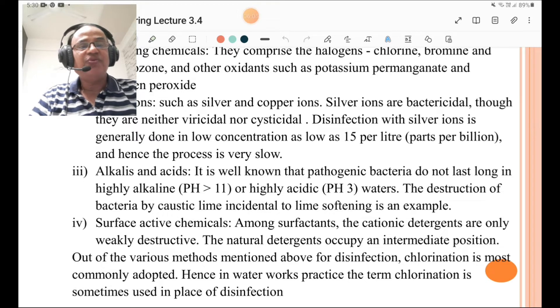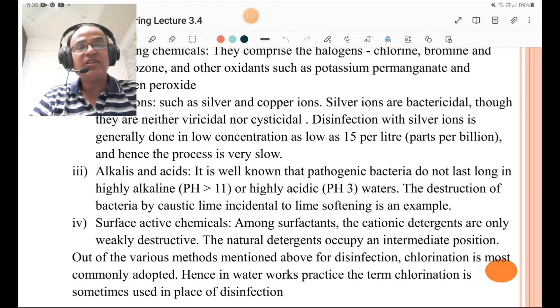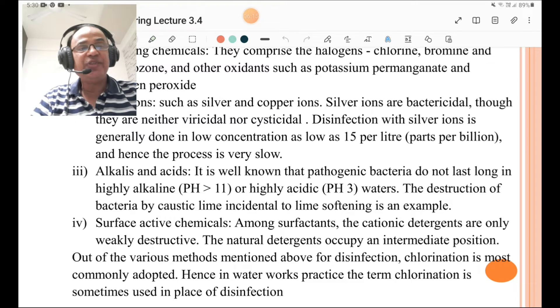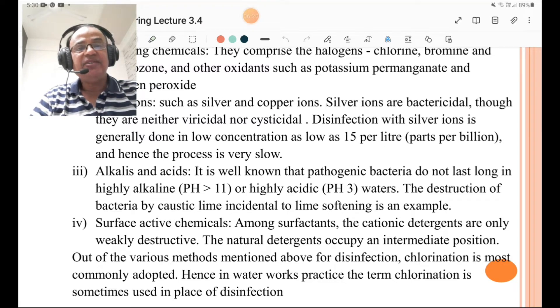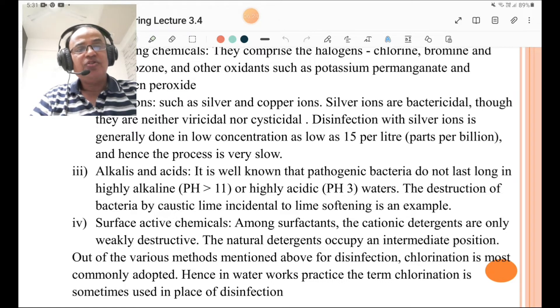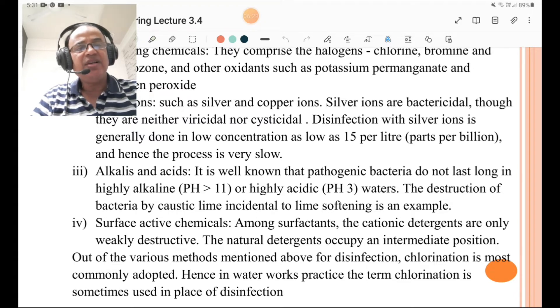Alkalis and acids: it is well known that pathogenic bacteria do not last long in highly alkaline water when pH is more than 11, or highly acidic water when pH is less than 3. The destruction of bacteria by caustic lime, incidental to lime softening, is an example. Surface active chemicals are also included among the chemical methods.